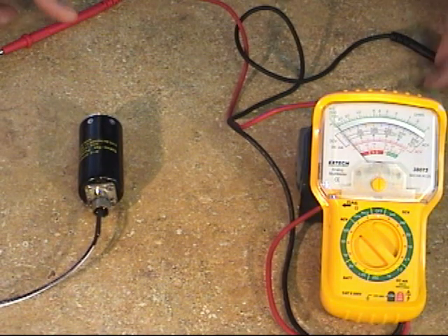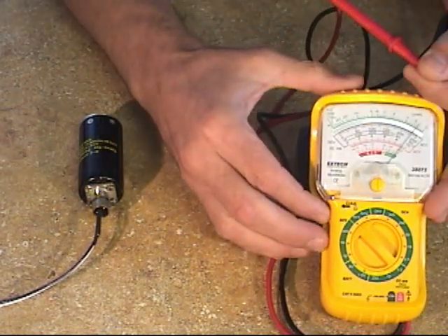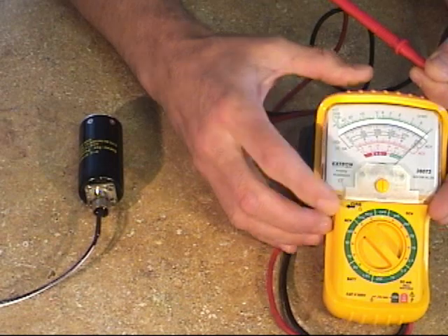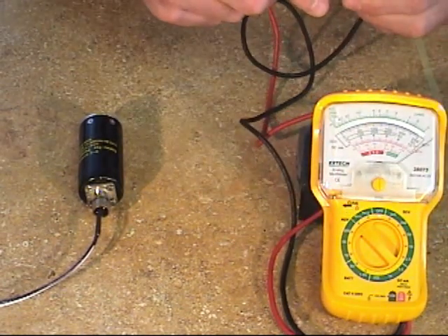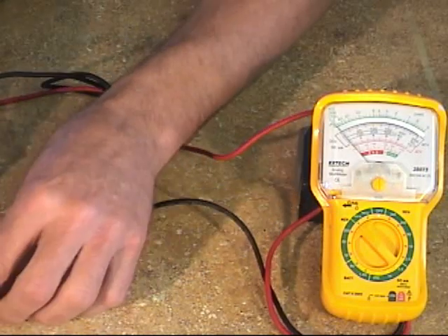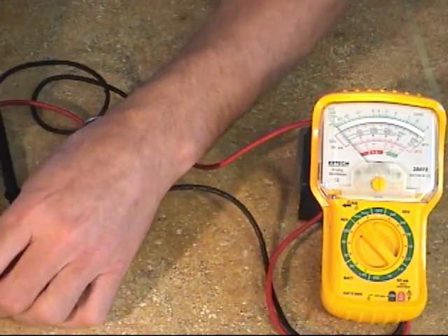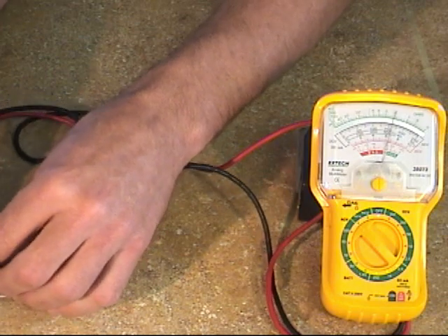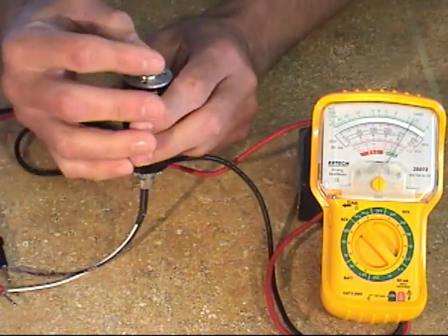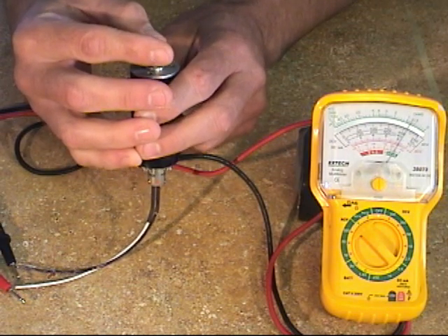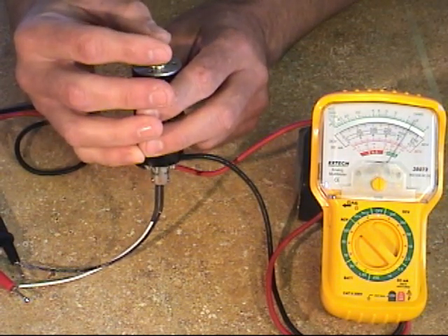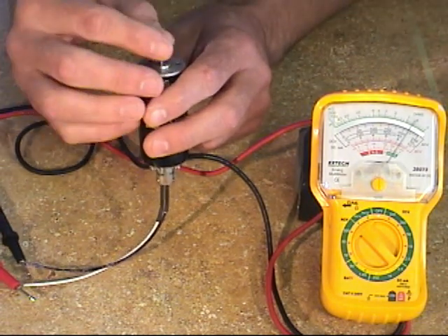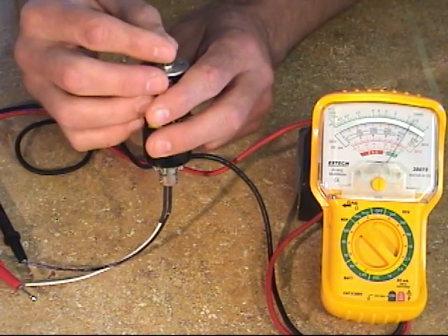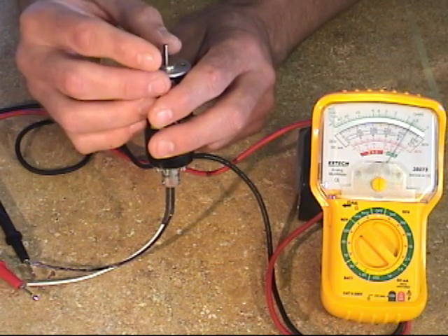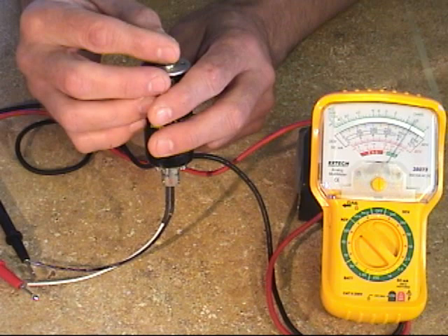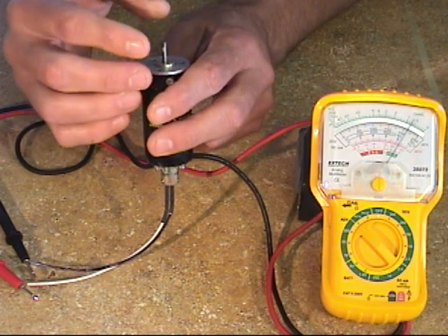Okay, next we're going to do a little resistance check with an analog meter. Of course, the first thing we're going to do with the analog meter is zero the ohm scale. Set to ohms times 1 here, and then zero the scale so it reads correctly. We'll be sure and preserve our correct polarity here, and do a little resistance check. Same drill. We'll turn it just 1/10 of a turn, and we'll watch. And I'm seeing about 50 or 100 variation here, which is not great. What I'm looking for is one clock position here that is greatly different than every other clock position. And these are all very similar.